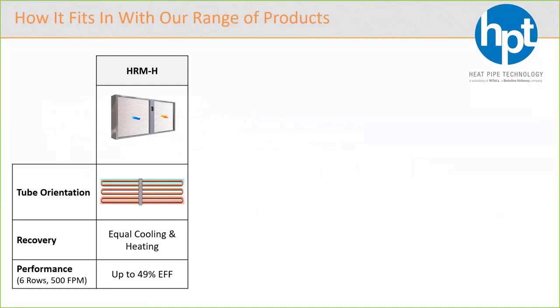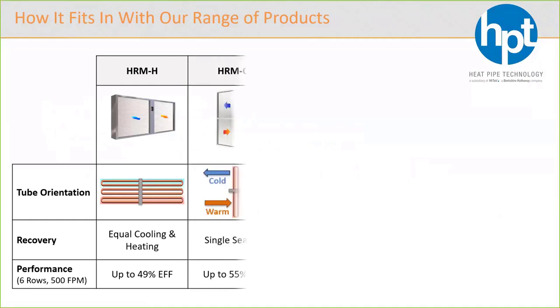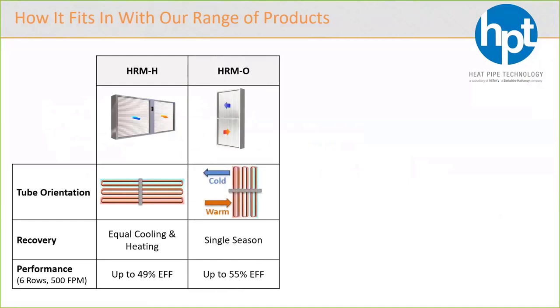So the original model that we came up with was the H, and that has equal cooling and heating, where the pipes are horizontal. We can also turn it 90 degrees and use gravity to help get the best performance, and that's up to a 55% effectiveness. But it is single season. You see the warm air has to be on the bottom.